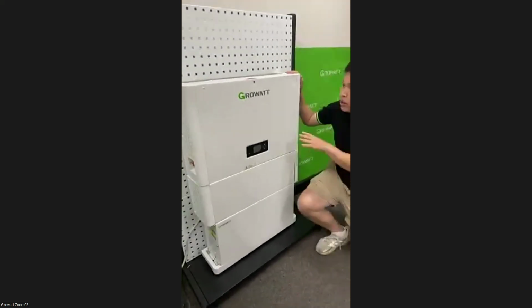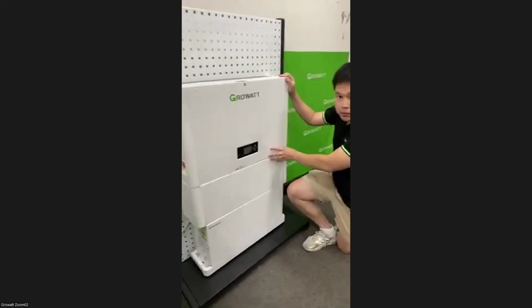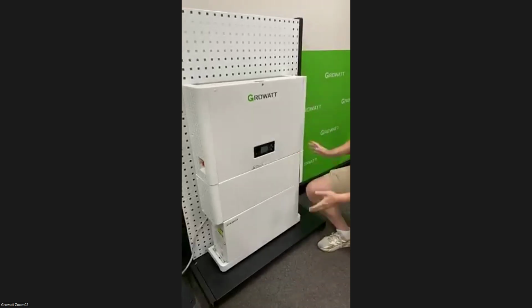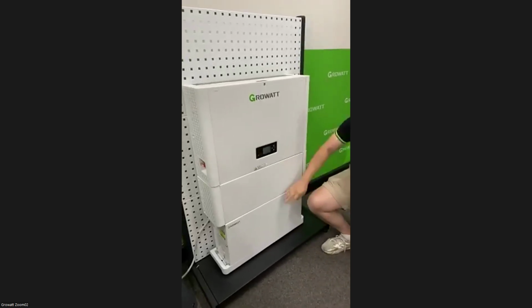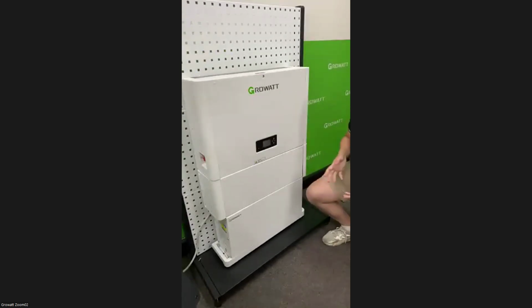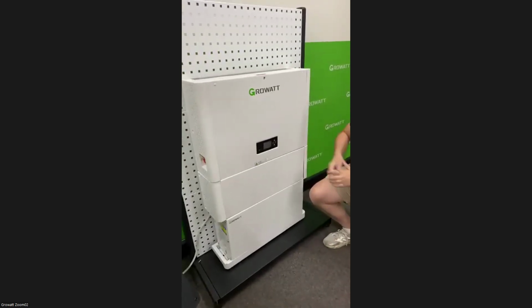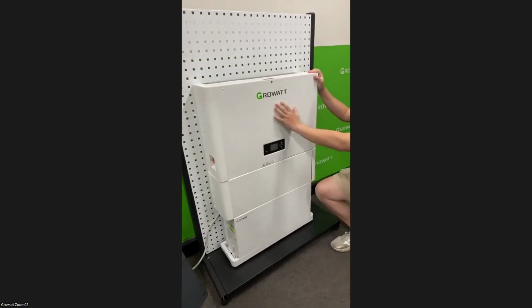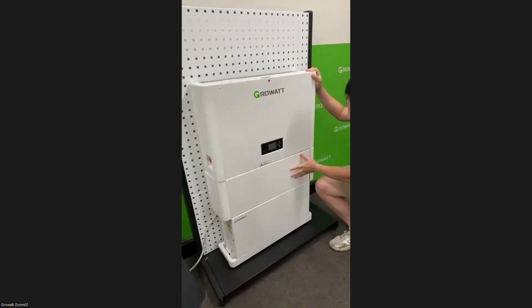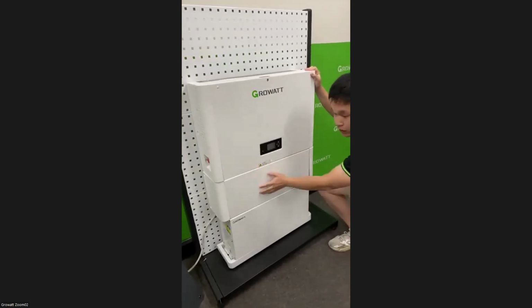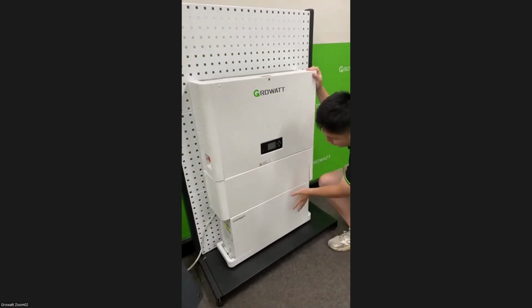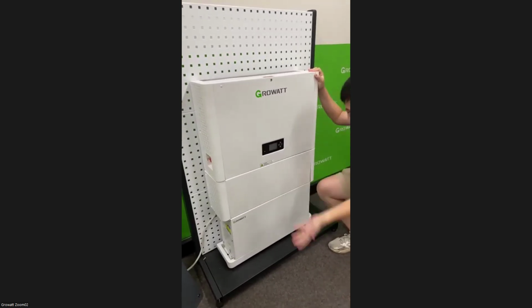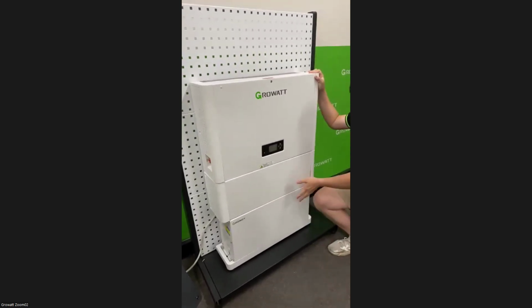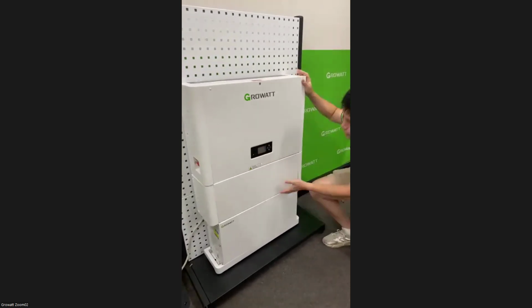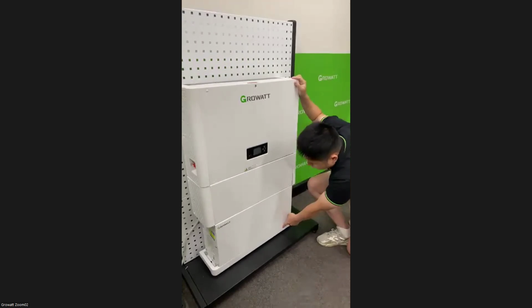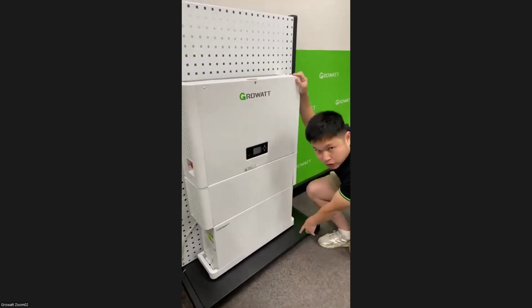So I'm Brian, and this is our SPH-HUB inverter system. As you can see, we have one battery included. To have this system, you must install at least one battery out of the 8 batteries mentioned earlier. At the top we have the inverter, and in the middle, this is the connection box where all the connections happen. Underneath the connection box is the batteries, so if you have more batteries, this keeps stacking them like playing with Legos. At the very bottom, since this is a ground level installation, there is a base plate to avoid direct contact between the batteries and the ground.